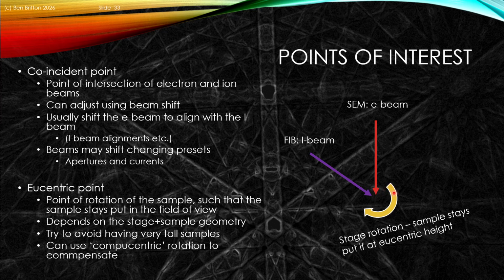What we'll also do is we'll rotate the sample effectively to enable us to have the sample perpendicular to the FIB or perpendicular to the SEM, the surface of the object. And we'll use a stage to rotate. We'll typically use probably a compucentric stage rotation. Ideally, we would like this to be eucentric, so as the system rotates, effectively the object stays put. And so that's what the eucentric point is, and eucentric height is to enable that to happen. So we can optimize the point of intersection, the coincident point intersection between the electron and ion beams. We can adjust this using beam shifts. Typically, I would suggest that you want to use the SEM beam shifts to enable that to be done, because the FIB beam shifts can change a few things like the shape of the probe that will do the milling, etc.